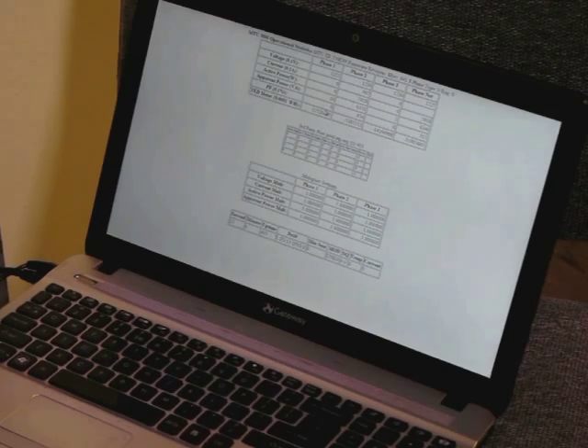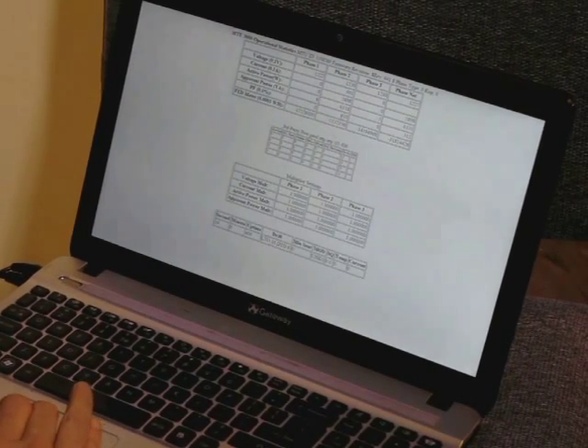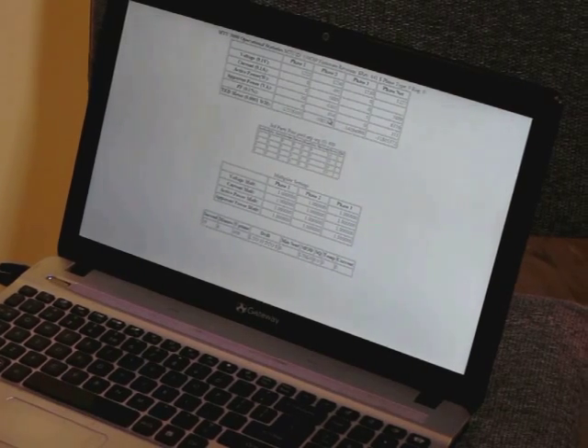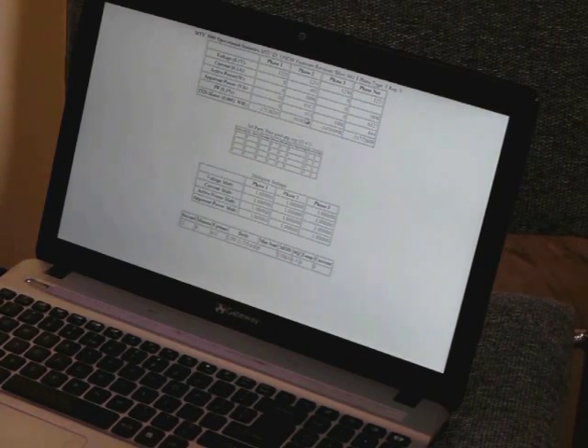My active power went positive, as you can see. 5918. And my power factor is at 93%, which is typical. Okay. So I'm pretty sure that's the B phase.